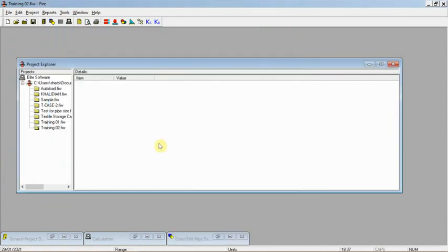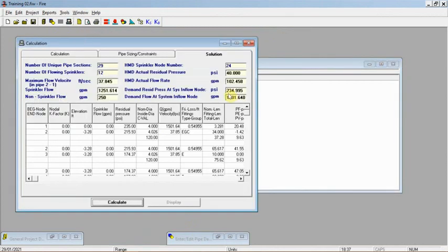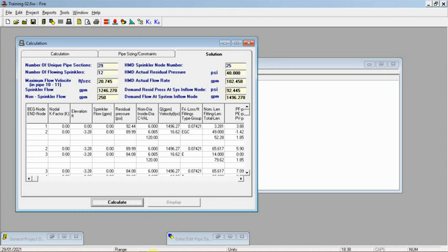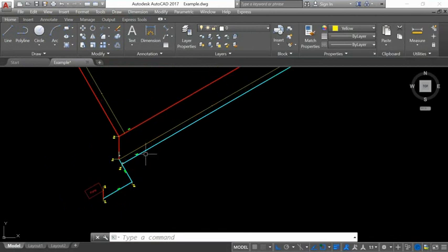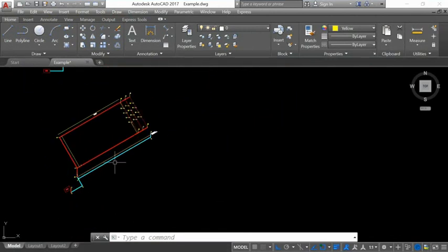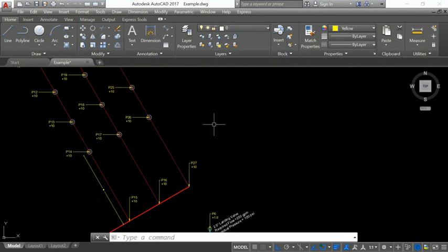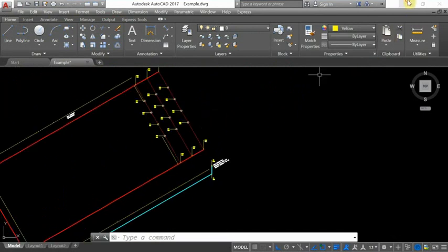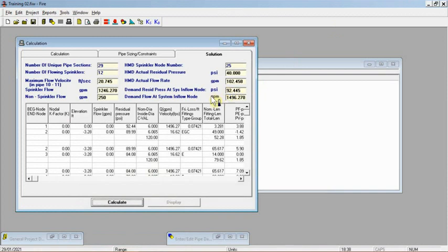After changing all 4-inch pipes to 6-inch in the underground and main loop, I execute and recalculate. The previous pressure was 235 psi. With the new pipe sizes, the maximum velocity is now at or below 20 fps and the pressure is below 100 psi. The final pipe sizing for the system is: underground = 6 inch, main loop = 6 inch, branch lines = 2 inch. The pump requirement is now 100 psi at 1500 gpm. The system is fully calculated and a report can be generated.